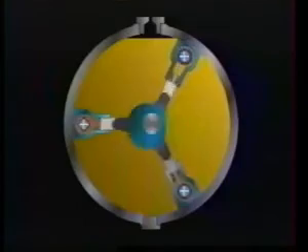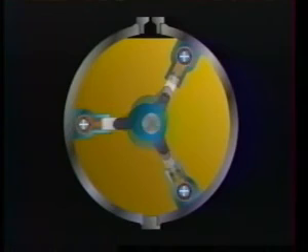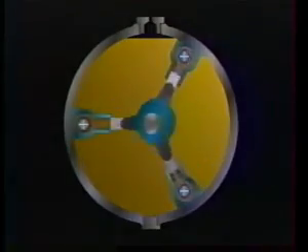The high-pressure water from the cylinder is directed to a collection manifold before going on to the working nozzle. High speed combined with a multi-diaphragm radial layout leads to a family of pumps of compact yet uncomplicated design. Pressures up to 700 bar or 10,000 pounds per square inch and flows up to 150 litres or 33 gallons per minute are available from this design.